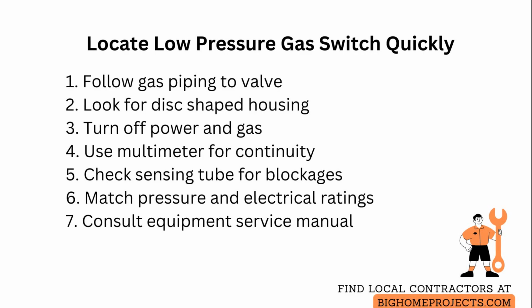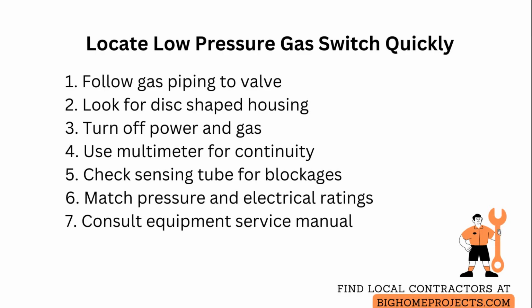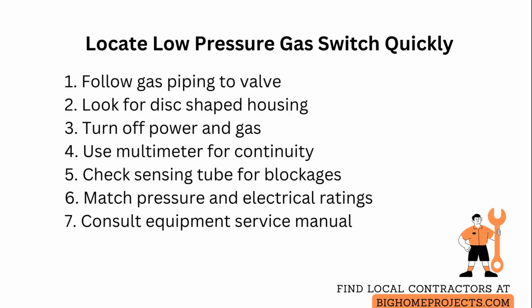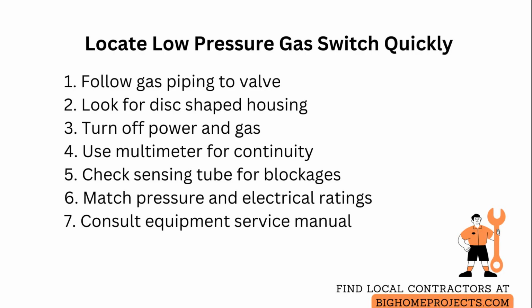The switch is often secured to the valve body or a nearby bracket and sits in the low-pressure tap or sensing line. It usually has a circular or disc-shaped housing about the size of a coin and 1 or 2 insulated conductors that connect to the furnace or furnace control board.